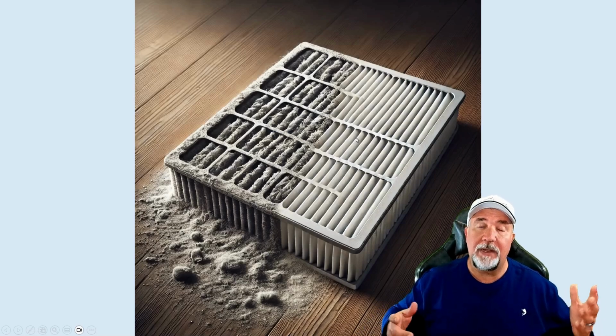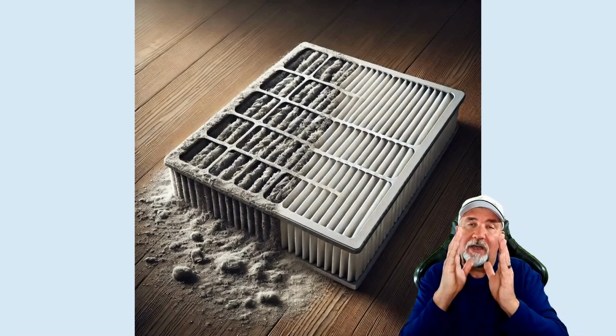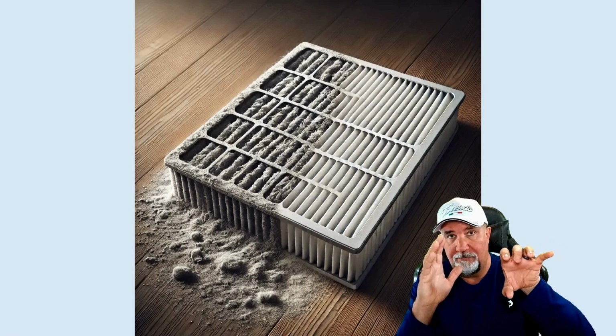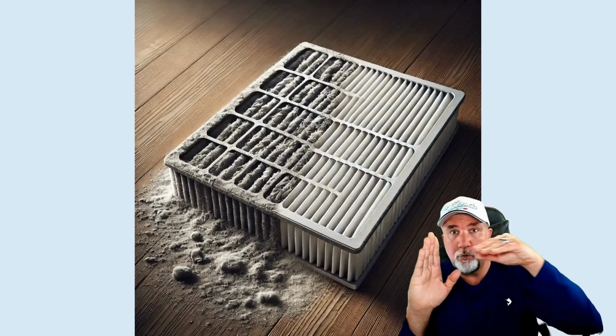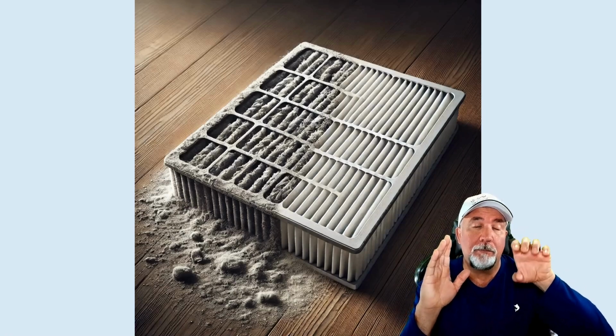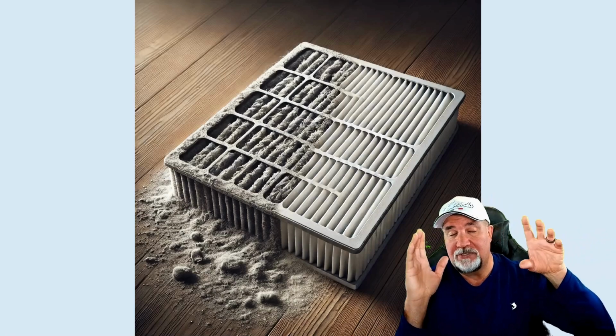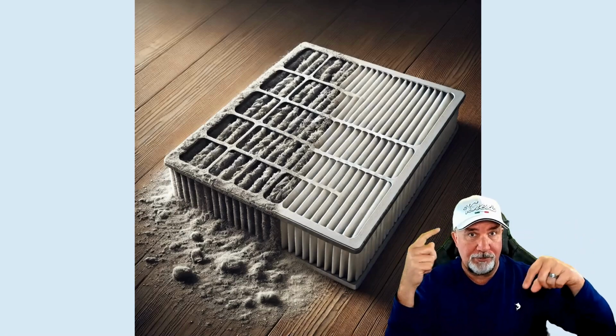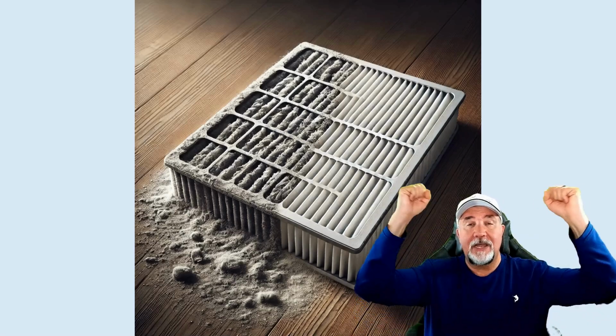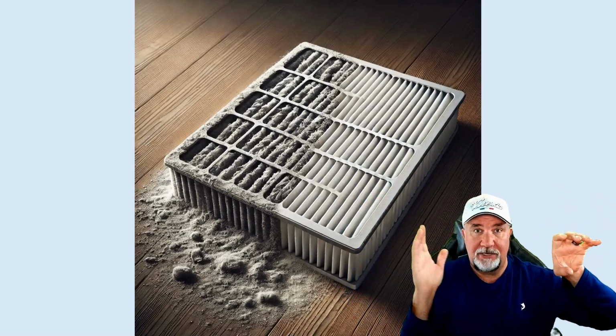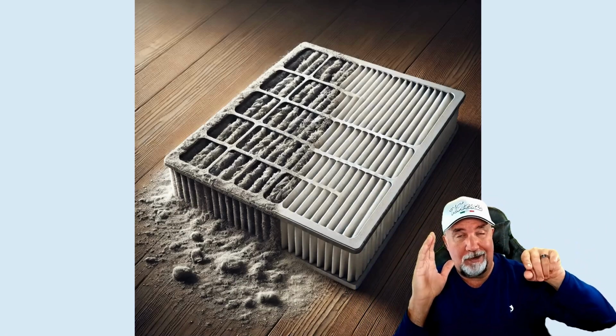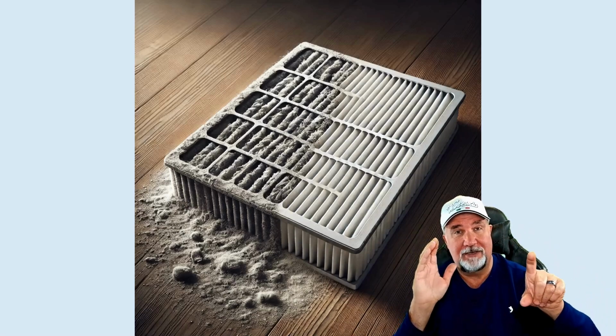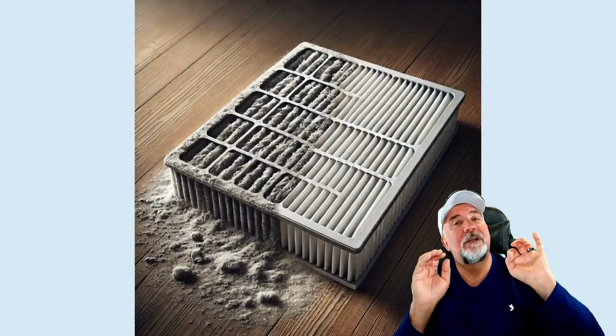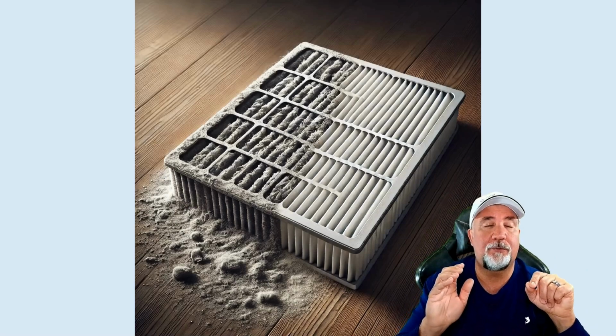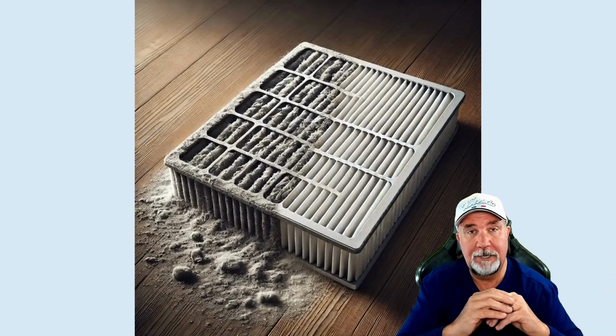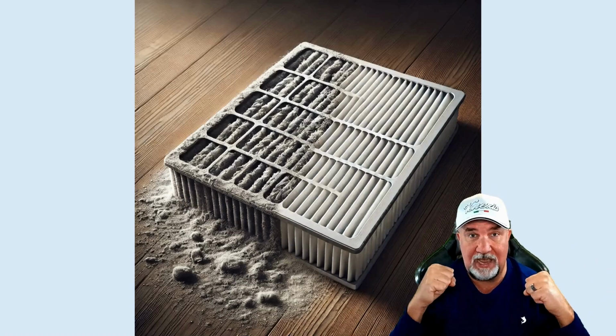Now, these are good, but the problem again is that as the air goes across, if your air handler is not powerful enough and the ductwork's not large enough, you're going to create too big of a restriction, and you're going to have problems with the air handler. It's not going to be able to handle it. If it's a variable speed unit, those motors are designed to ramp up as high as they possibly can to maintain the amount of air they should be pulling. So if you have an air handler that's super, super noisy, there's a good chance that your ductwork is undersized, or you have the wrong size filter in there, or the filter is restricting it too much. That causes that motor to scream that it just can't handle it anymore.